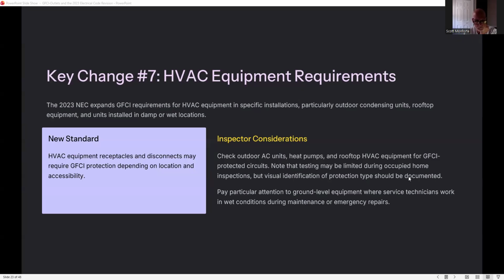Inspector considerations. Check outdoor AC units, heat pumps, and rooftop HVAC equipment for GFCI protected circuits. Note that testing may be limited during occupied home inspections, but visual identification of protection types should be documented. Pay particular attention to ground level equipment where service techs work in wet conditions during maintenance or emergency repairs. So I guess your split system outside needs to be on a GFCI breaker, and any condensers, that kind of thing.